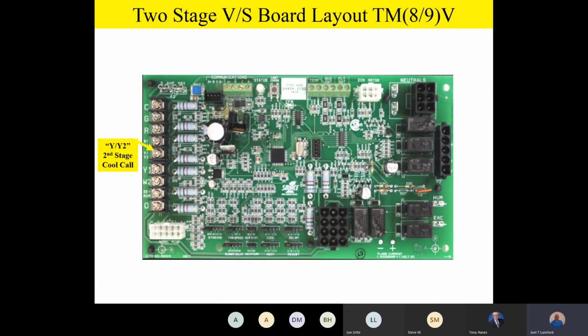Now please write this down or make a mental note of this. If this board sees a Y/Y2 input on this terminal, it drives the fan to 100% cooling airflow. Let me say that again. If I get a 24-volt signal on Y/Y2, it drives the fan to 100% cooling airflow. However, if it sees a Y1 call all by itself, with a cooling call now, it's going to drive the fan to 65% of whatever cooling airflow you've got set up on the board. So a Y1 call is 65% of your total cooling airflow that you've got set up on the board. A Y/Y2 call is 100% airflow.